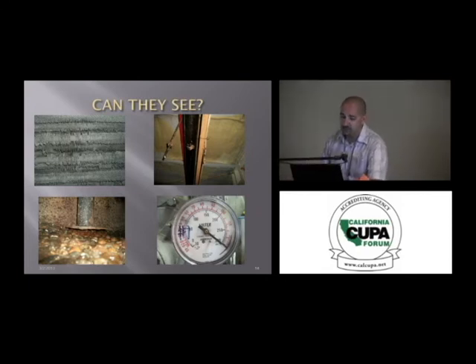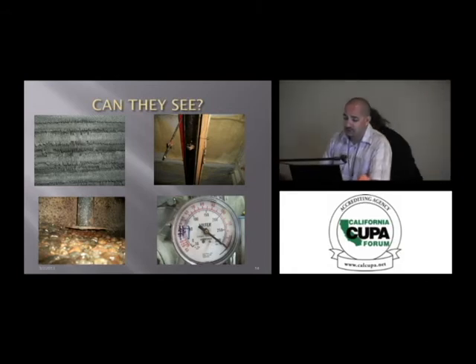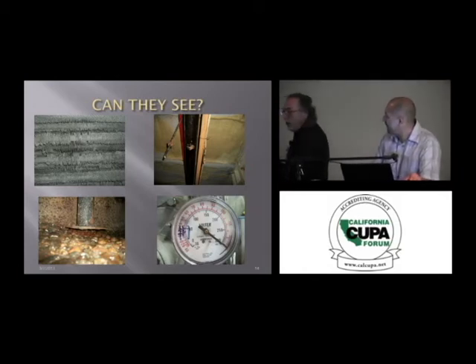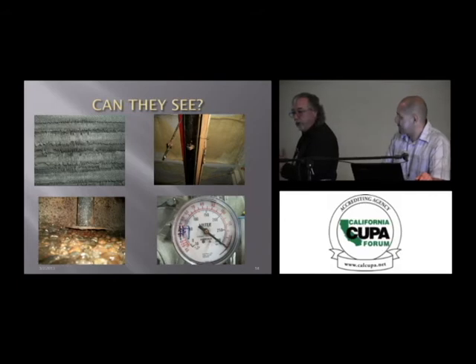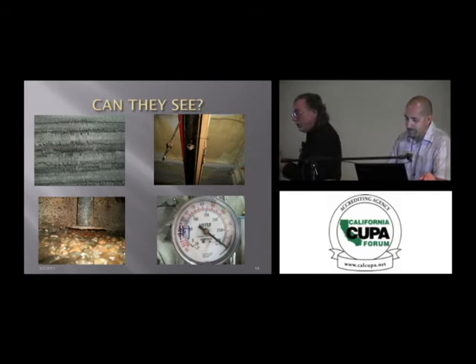Coils, this is a spiral fin coil, the picture on the top left-hand side. Corrosion, SO2 gas eats away at everything. Could be bad water as well. I believe this particular facility was using ditch water to defrost.